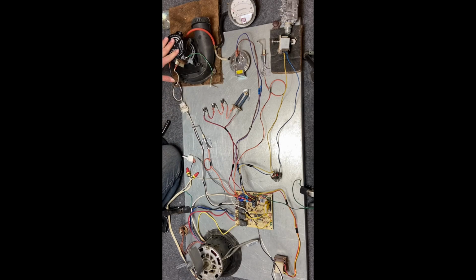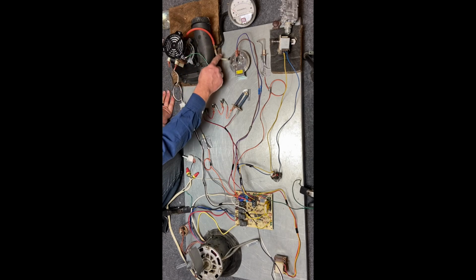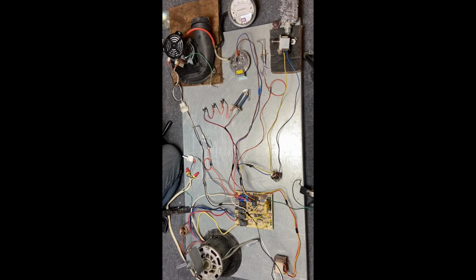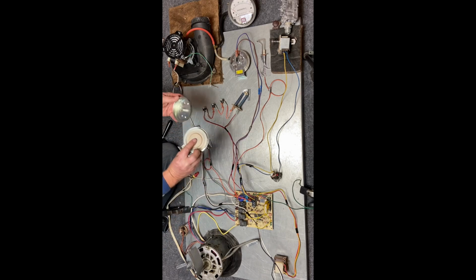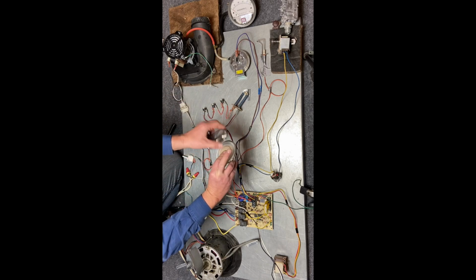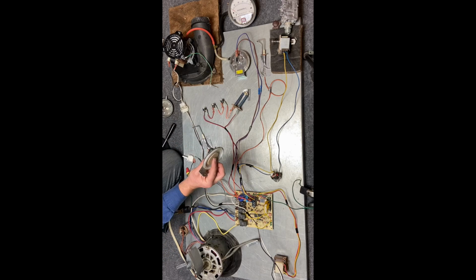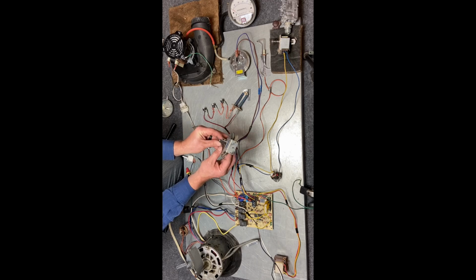Now what's great about this motor is when it runs, it's pulling a vacuum. So it goes through a pressure switch over here. So it pulls a vacuum to this pressure switch. This pressure switch is just simply a switch. If we take this apart, we can see the hose is here. There's going to be a little spring that keeps this pushed up. If we look at this pressure switch and we take it apart, we see the hose hooks into the side and there's a spring in here that keeps this pushed up. And this is nothing more than a little micro switch right here.